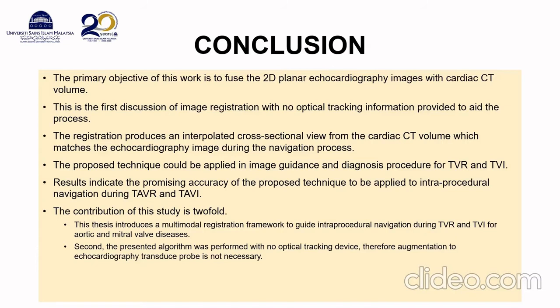The primary objective of this work is to fuse the 2D planar echocardiography images with the cardiac CT volume. This is the first discussion of image registration with no optical tracking information provided to aid the process. The registration produced an interpolated cross-sectional view from the cardiac CT volume, which matches the echocardiography image during the navigation process. The proposed technique could be applied in image guidance and diagnostic procedures for valve replacement and valve implantation. The result indicates promising accuracy of the proposed technique to be applied to intra-procedure navigation during the replacement and implantation procedure.